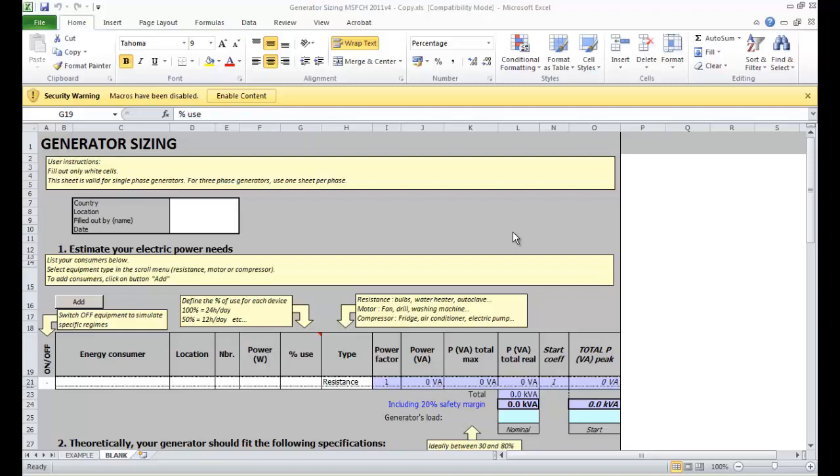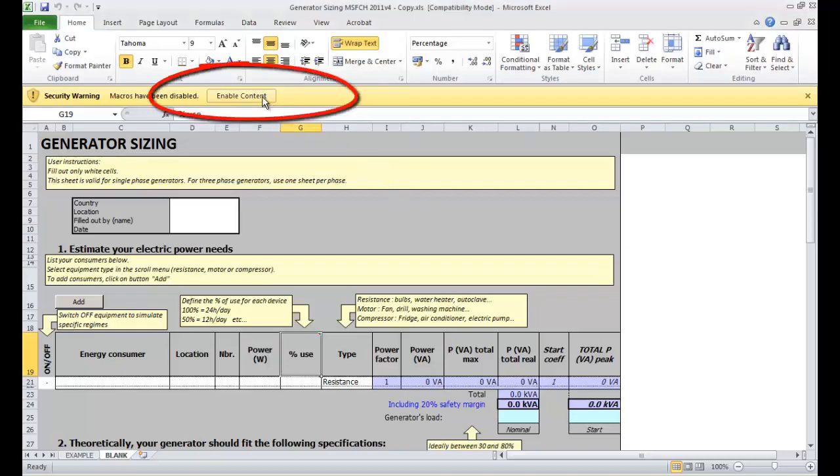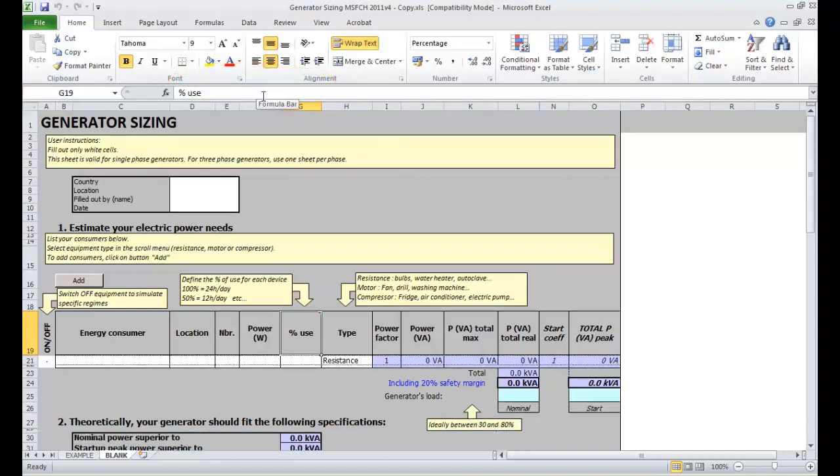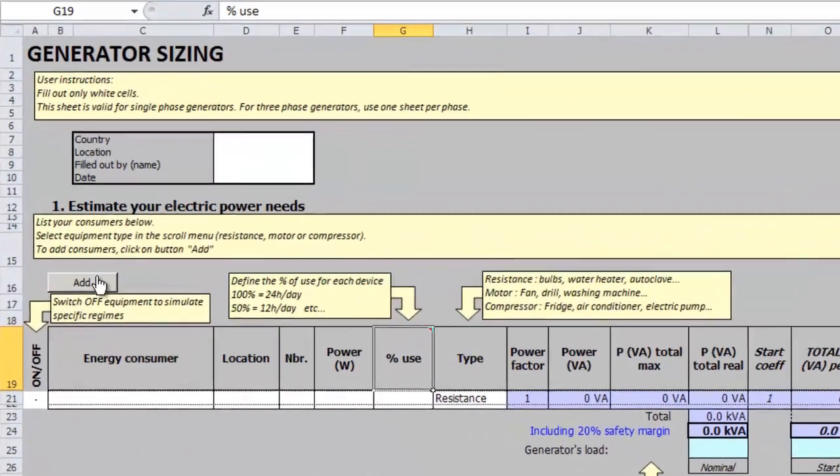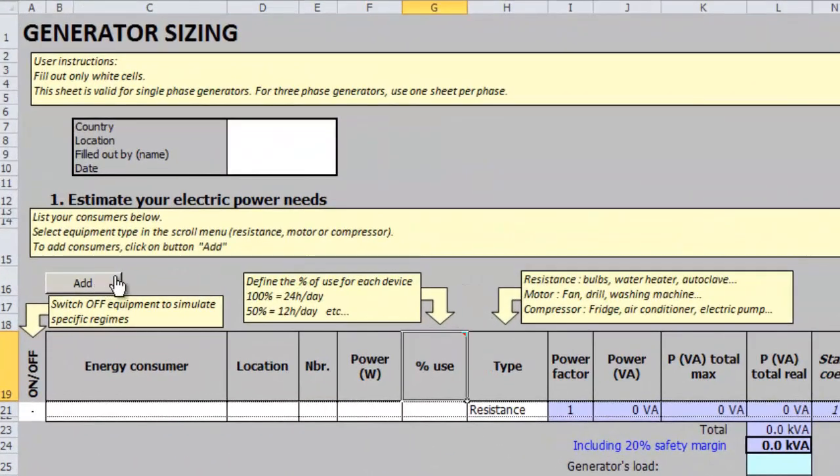The use of this tool is a must when selecting a generator and we should pay close attention when filling it because if not it can mislead us into having a too big or too small generator for our installations. Before filling the Excel file we need to have all the data concerning the electrical consumption of our installation. For this we shall make an exhaustive list of all the electrical devices present in our installation and their power consumption.